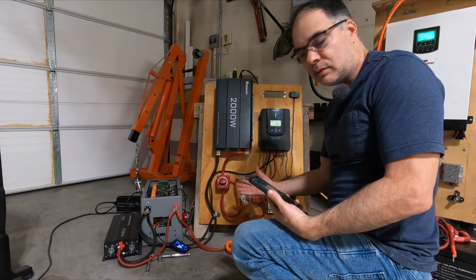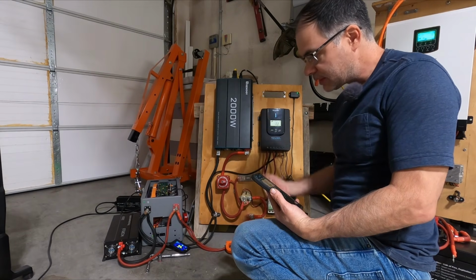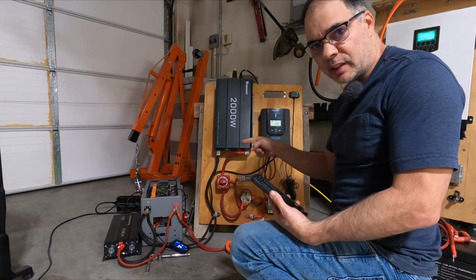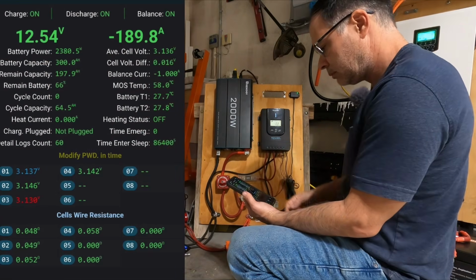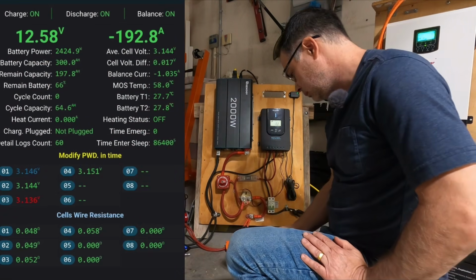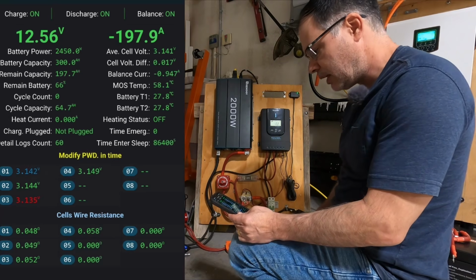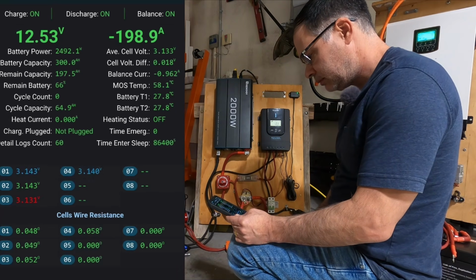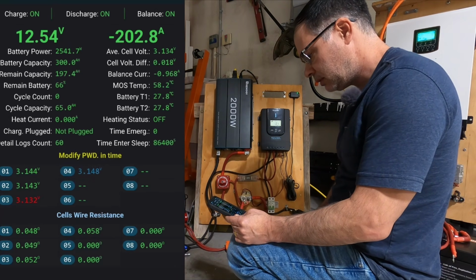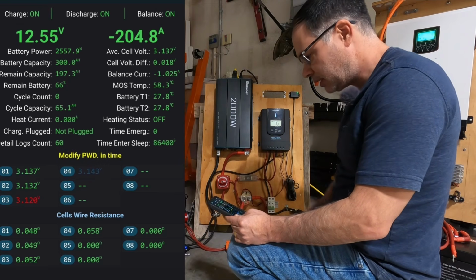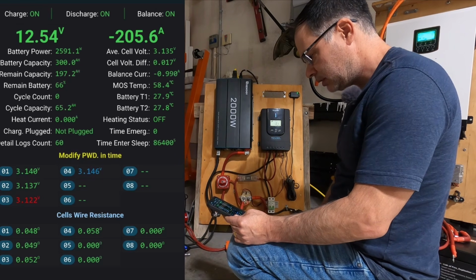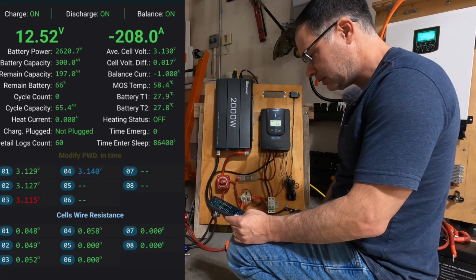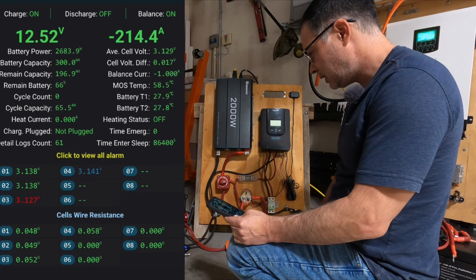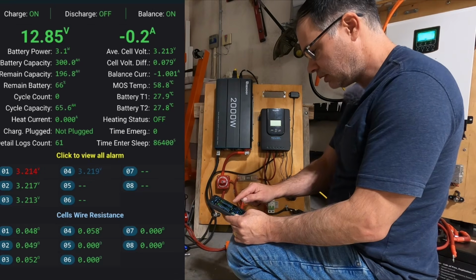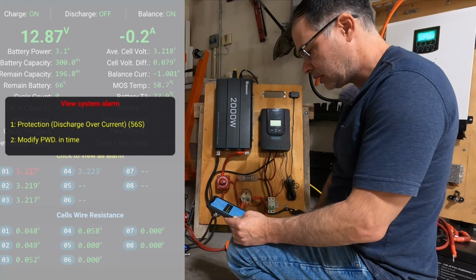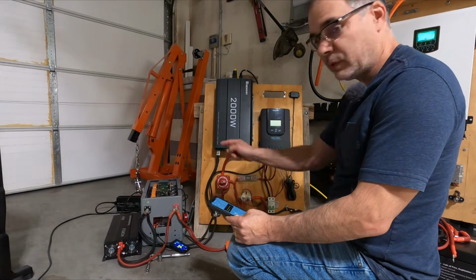All right, next we're gonna purposely drive up the current and we're gonna see if we can surpass and trigger the overcurrent protection. 194, 195, 200. Hopefully we don't blow the fuse in there. 206, 205, 208, 214. There's your alarm. So we got discharge over current, and we did not blow the fuse.